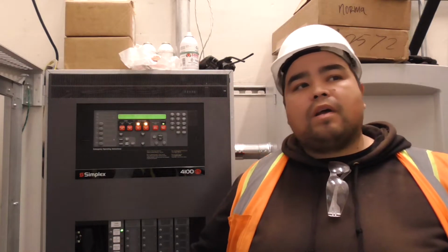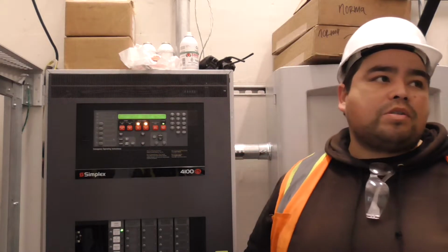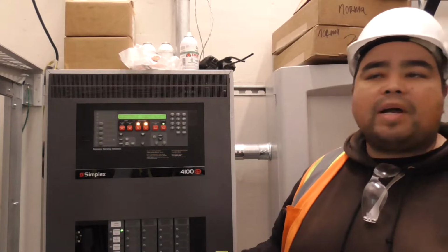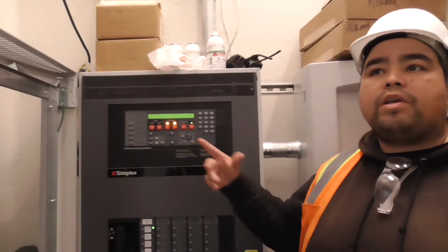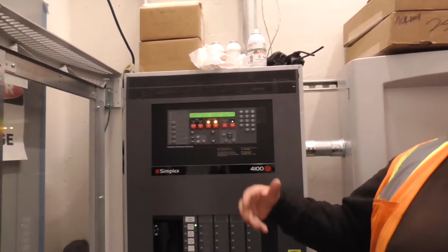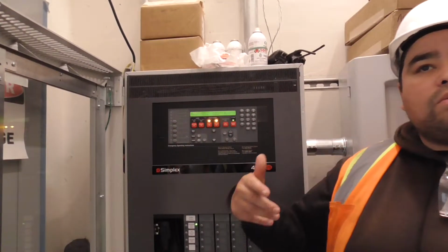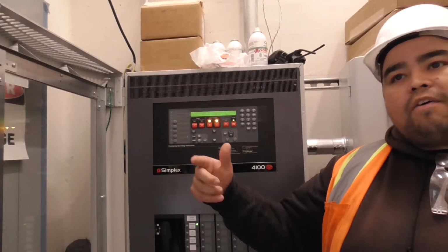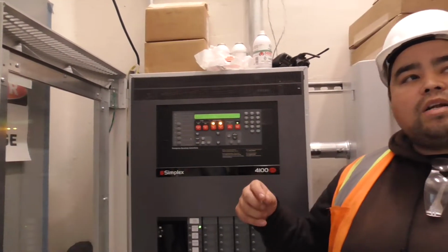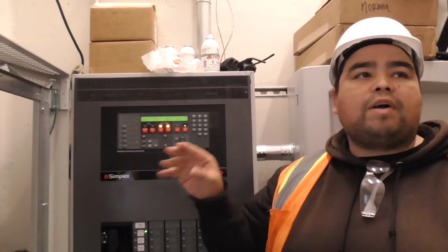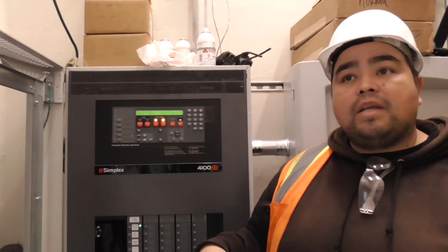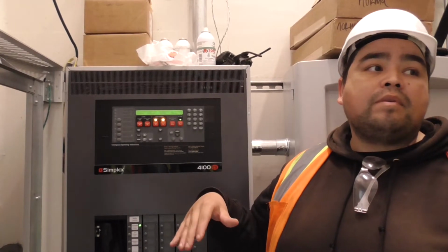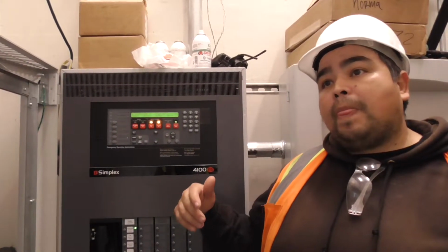There's a thing that probably does it every 8 hours. By default, if you have a trouble on it, it's called reoccurring trouble, or reoccurring supervisory. If somebody doesn't fix the problem, it'll reflash the supervisory at you, letting somebody know, hey, you haven't fixed the condition yet. In here, it's not like that, which is what I would think you prefer.